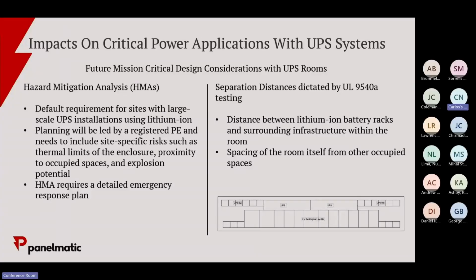Ideally you could do gas detection and fire suppression in the entire enclosure, but that's a more costly way to do it. So what most people are saying is push the batteries to one side of the enclosure, and then you just need fire suppression and gas detection in that specific area. It's also less airflow you have to recirculate because you're not trying to circulate the entire enclosure, just the battery area. So to follow up on my question earlier...